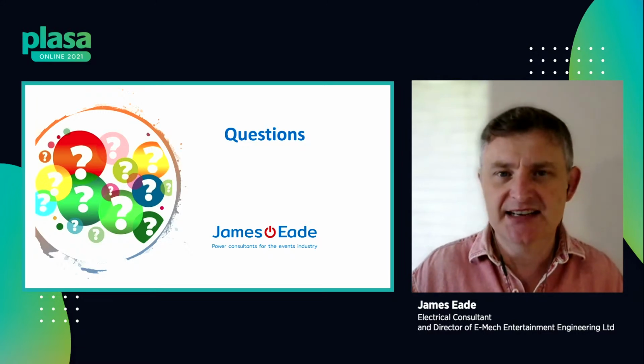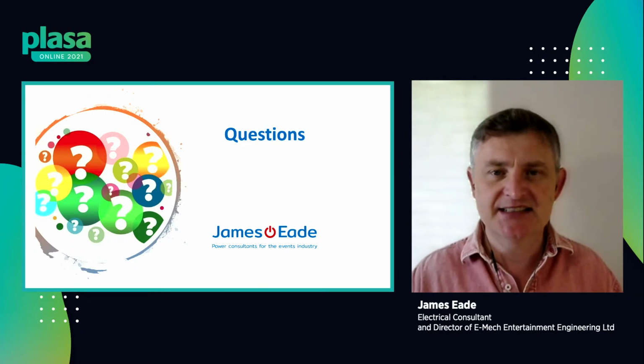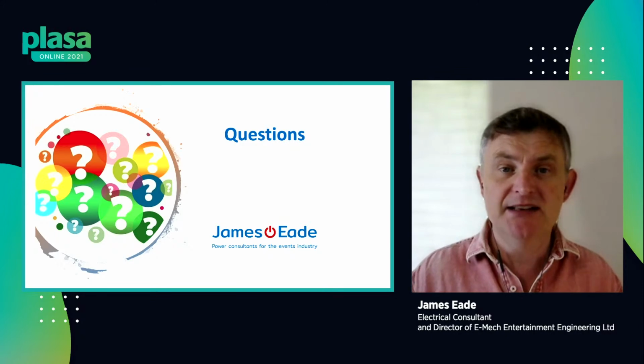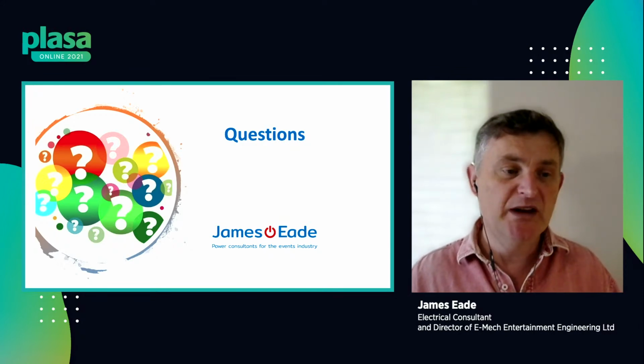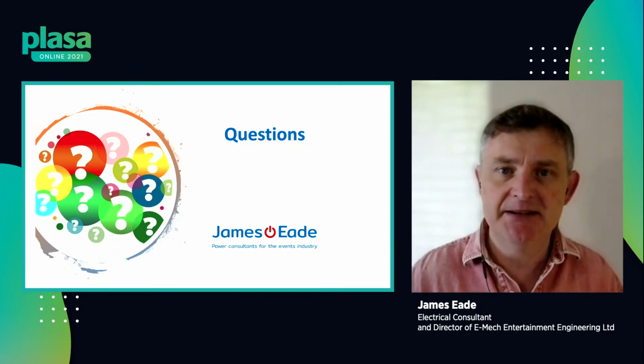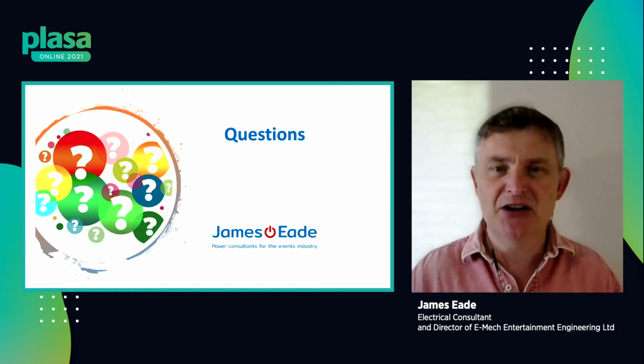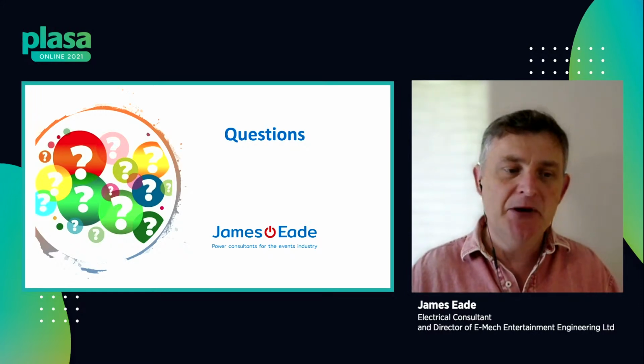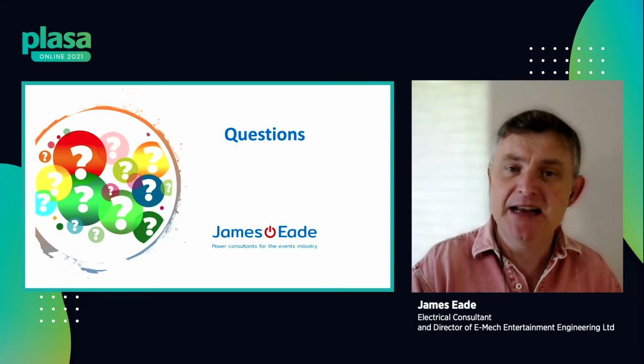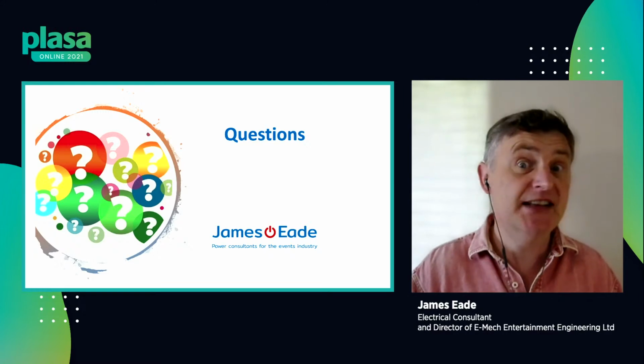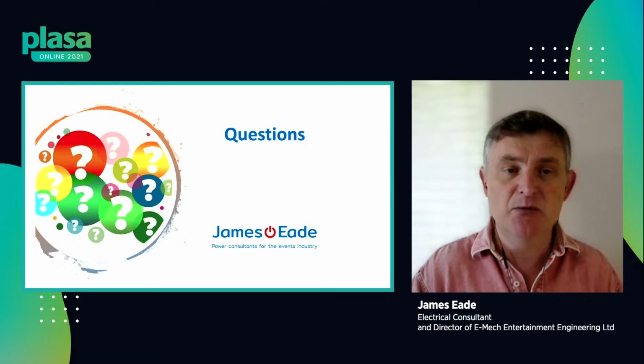Because dimmers come in channels of 6, distros come in blocks of 6, and 6 is a round number that we're quite familiar with in electrical distribution. We said no more than 6 items of kit on any one distro, because 7.5 is a bit harder to work with. But if you allow, like I say, a milliamp of leakage for every switch mode power supply, then you won't go wrong. Often it's much less. Some systems are designed very well.